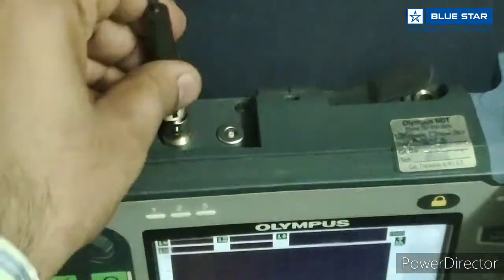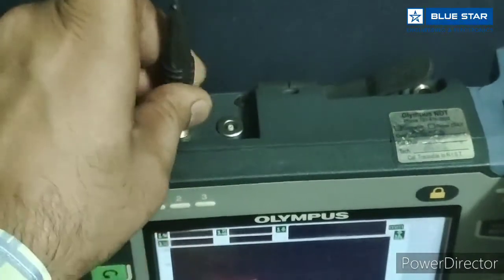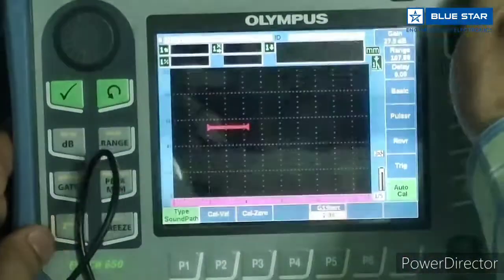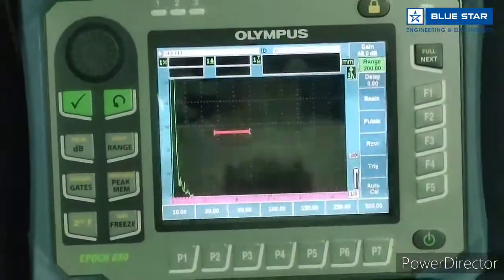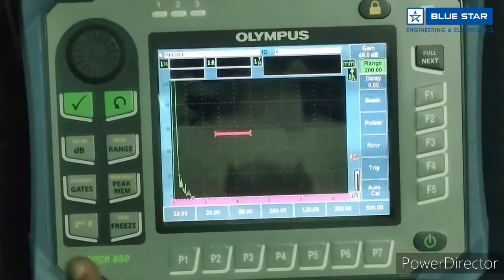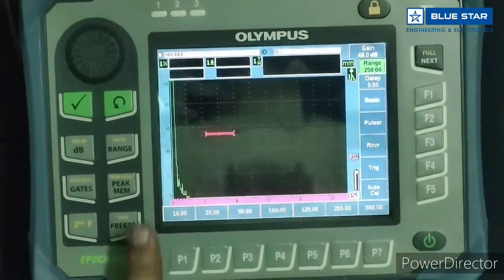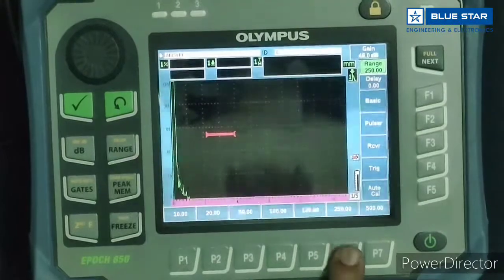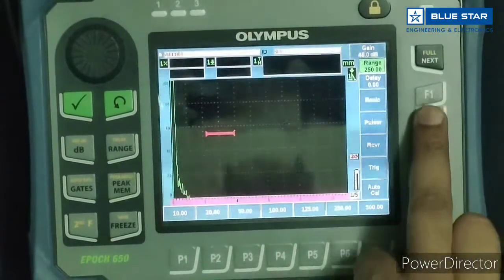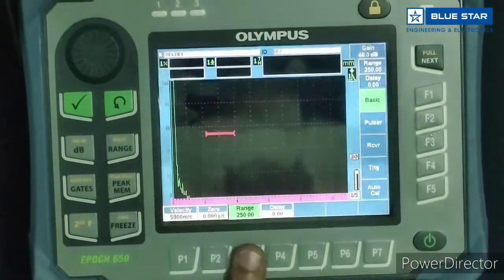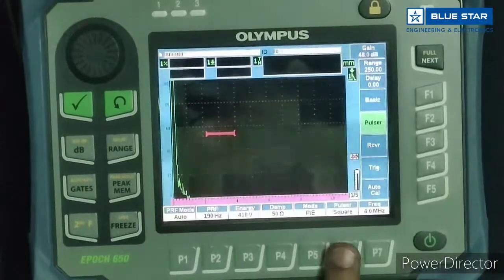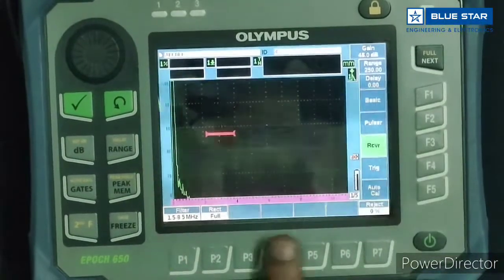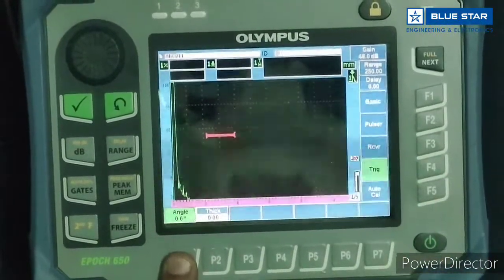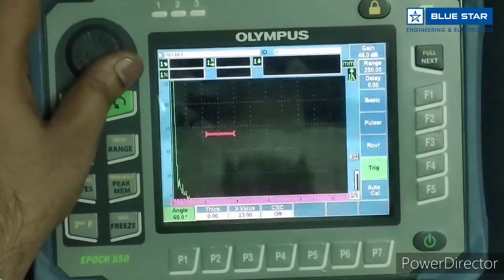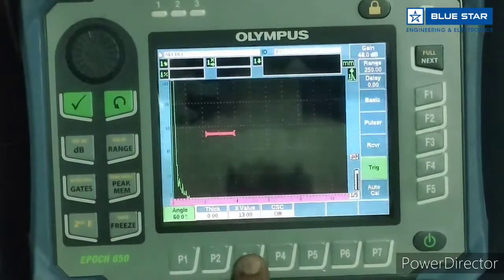Calibration of angle beam transducer. Connect probe in T-R socket. Range should be 250 mm. Go to basic and select range 250 mm. Pulser mode PE square 4 MHz. Filter 1.5 8.5 and angle should be as per the probe. I am using 60-degree angle probe.